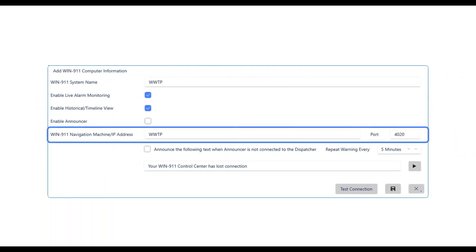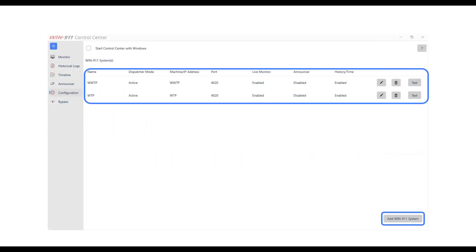The settings are pretty simple — you give a system a name, specify where that machine is located with a hostname or IP address, and the port it's running on. You can enable different features for each system you add. Once added, you can see all those different systems in your Control Center. If you're doing a redundant system with mirrored alarms, you can turn off alarms from the standby system so you're only seeing one particular set of alarms.